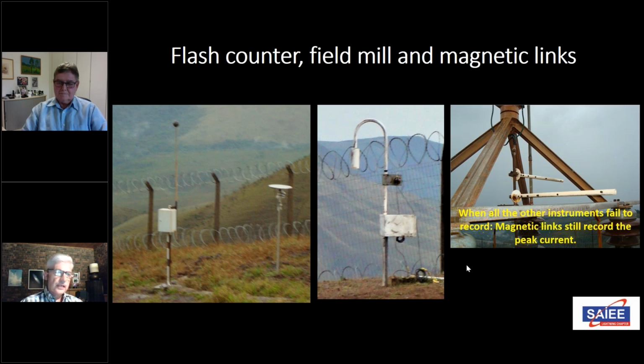One of the things Andrew meticulously did was ensure that even if this fell, and that fell, and that fell, there would somehow be some record of what happened. For example, there are spark gaps at the bottom of the tower, and if everything else fails, you'll see an etching of the spark gap there. In addition, we'd have a recording of the peak current that flowed in the conductor, recorded in these magnetic links, which are spaced as they are because of saturation—if they're too close and the current too high, they saturate.